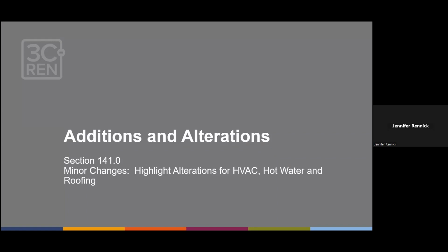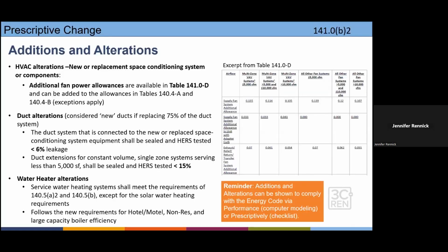For additions and alterations, we have a few slides here just to hit on a couple of the highlights. If you are working on additions and alterations, typically this part of the code section is fairly nuanced, and you'll want to go into the code section. It's not very many pages long, but it really just depends on what you're doing. So it's like, well, I'm completely replacing the HVAC system. Okay, what are the requirements? Oh no, I'm only doing a duct extension, for example, to serve an addition that's less than 5,000 square feet. Oh, okay, if that's the case, you only need to seal the ducts and HERS test it to less than 15% leakage, versus all new or replaced ducting systems, where you would test it to 6% leakage.